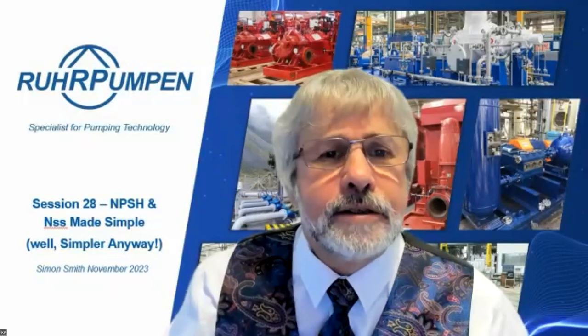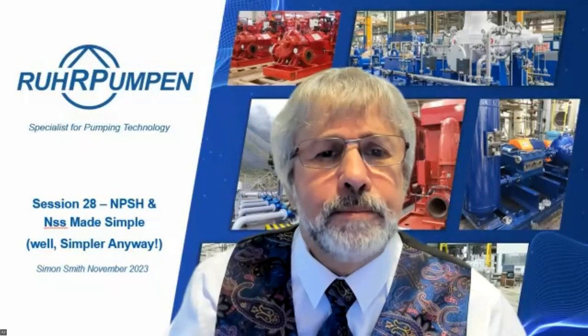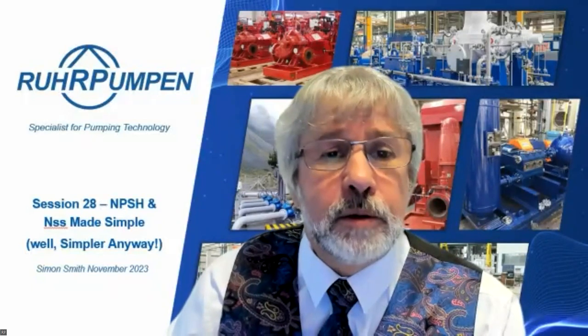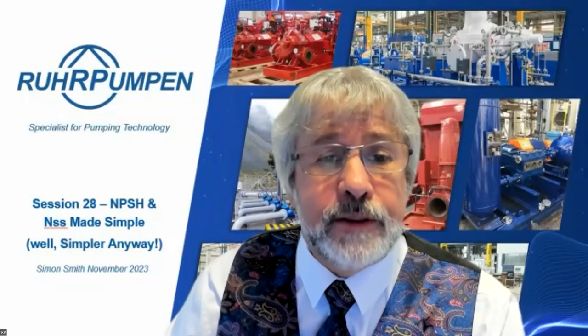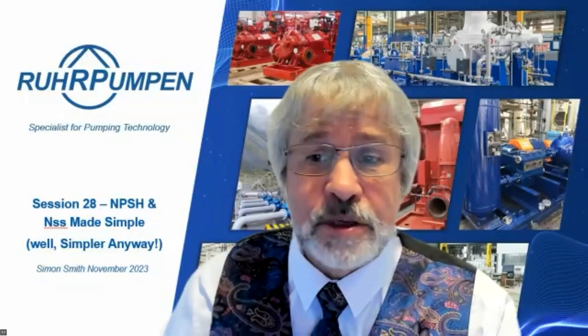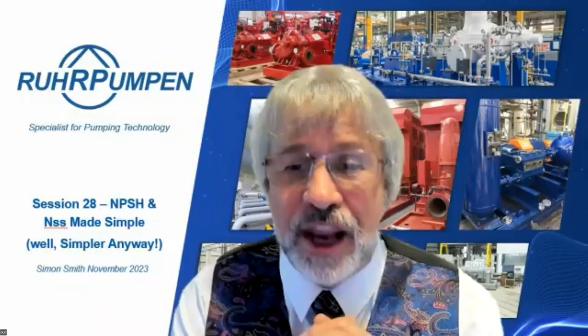Mikil Cipade asks: how will NSS be affected with respect to high flow rate pumps and the type of impeller? The suction specific speed of a pump is specific to that particular pump size and impeller. A big pump will have a different NSS number from a small pump, so you have to look at it on each individual pump.